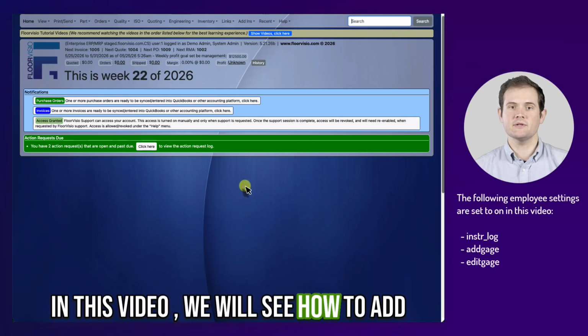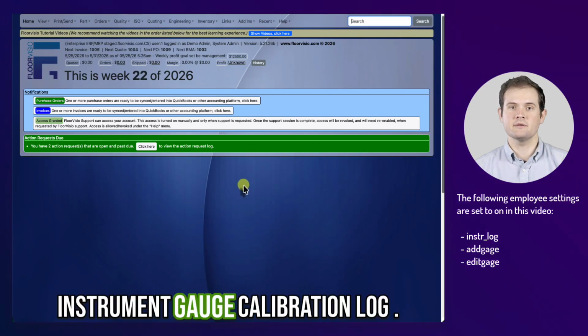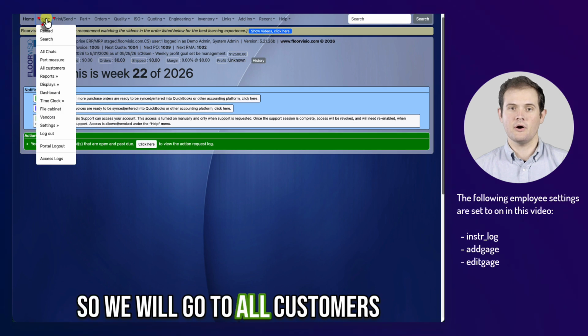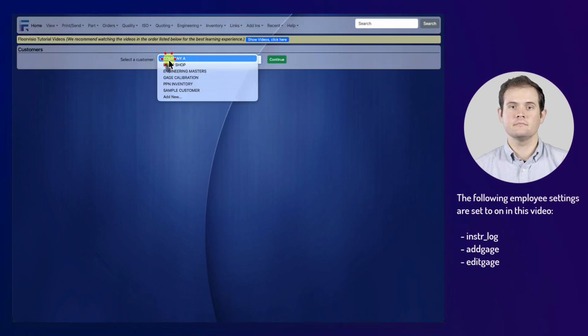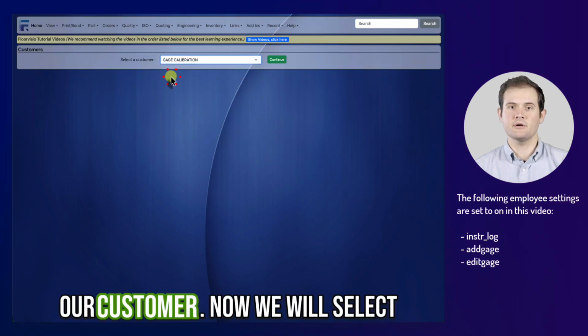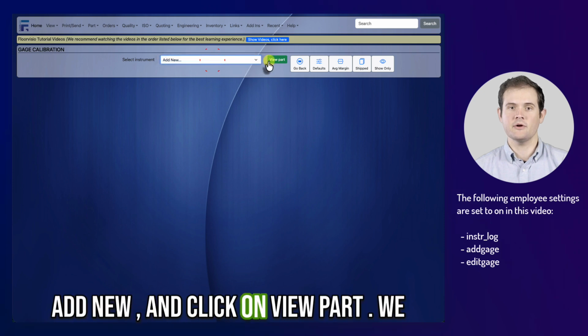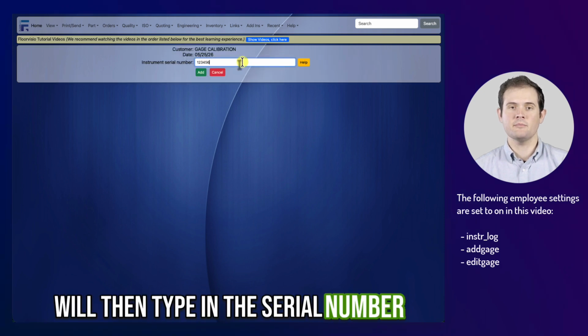In this video, we will see how to add a new instrument into your instrument Gage Calibration Log. So we will go to All Customers. We will choose Gage Calibration for our customer. Now we will select Add New and click on View Part. We will then type in the serial number for this gauge.